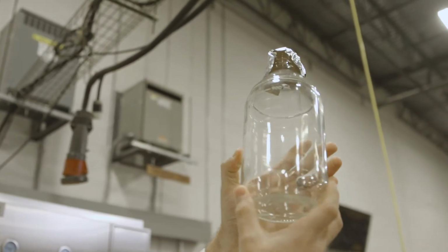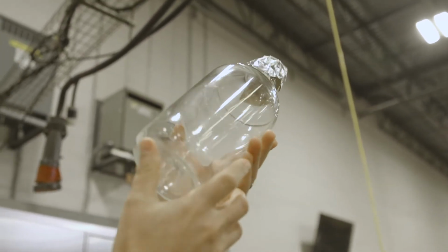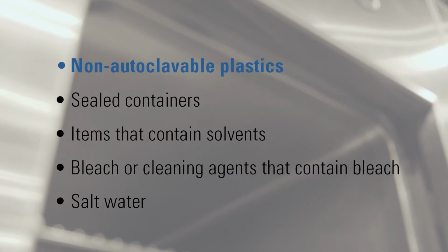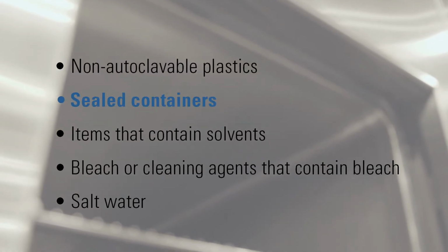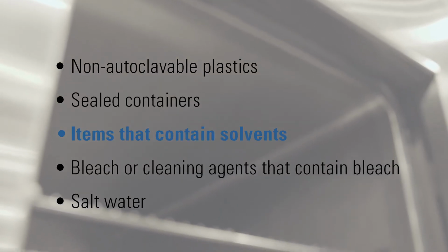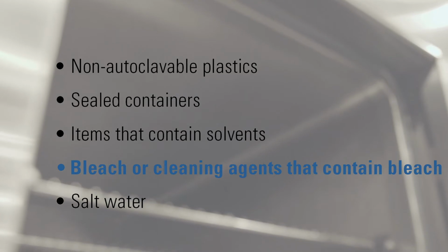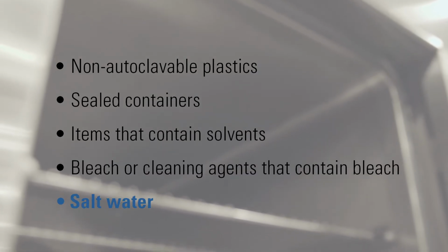As a rule of thumb, always inspect containers prior to loading to ensure that they are autoclave safe and, if they're glass, they don't have any cracks. Never place the following in an autoclave as they will cause damage to the chamber: non-autoclavable plastics, sealed containers, items that contain solvents, bleach or cleaning agents that contain bleach, and salt water.